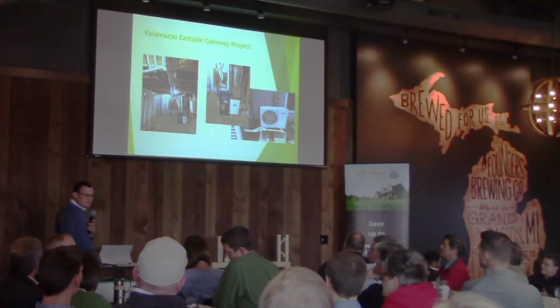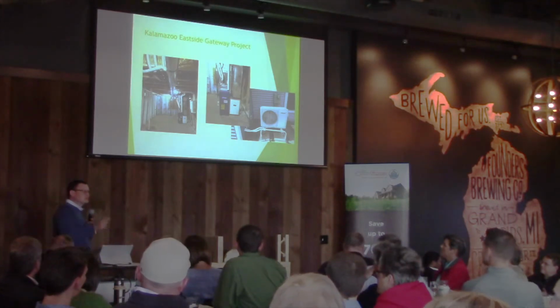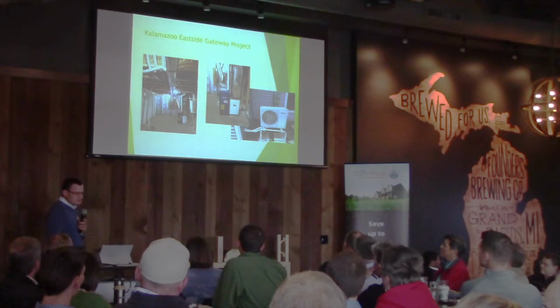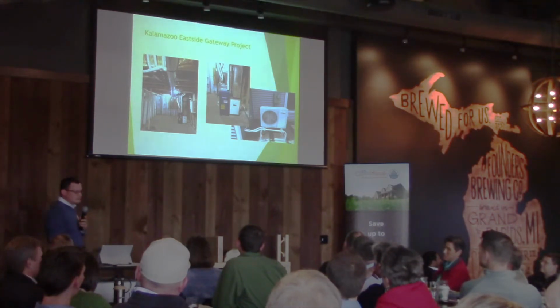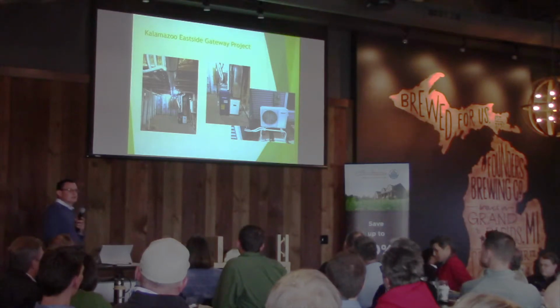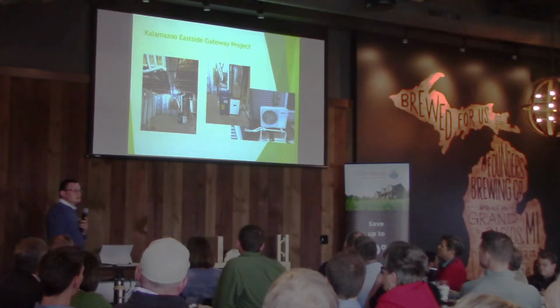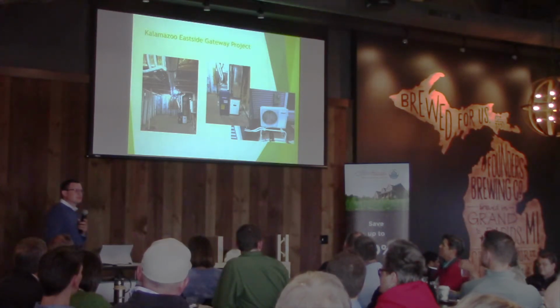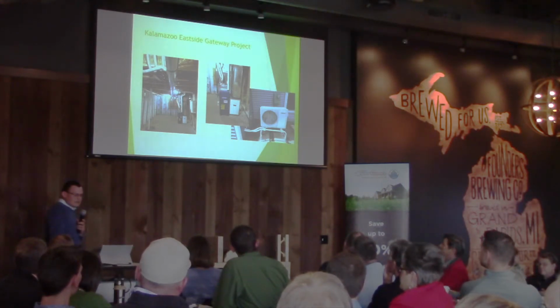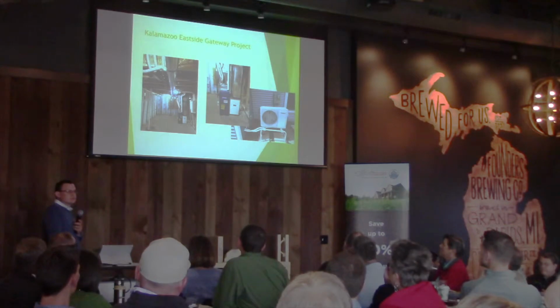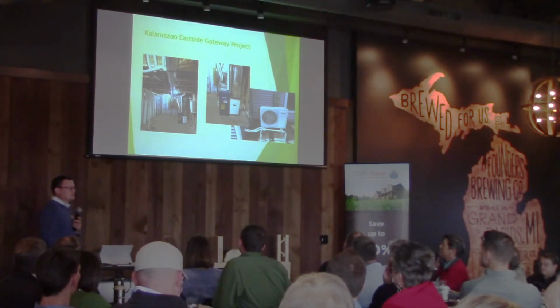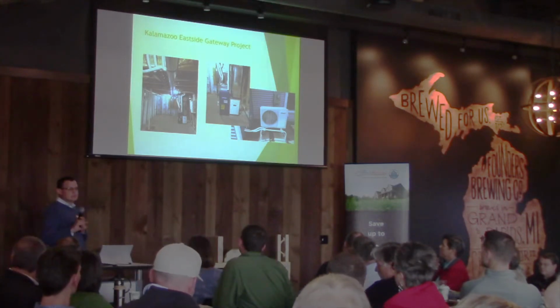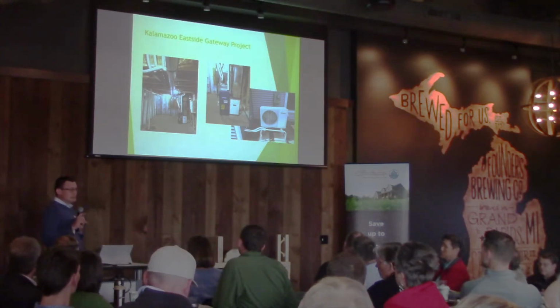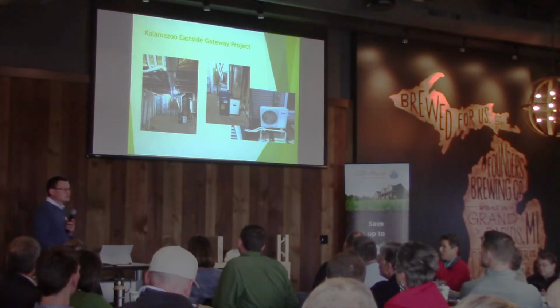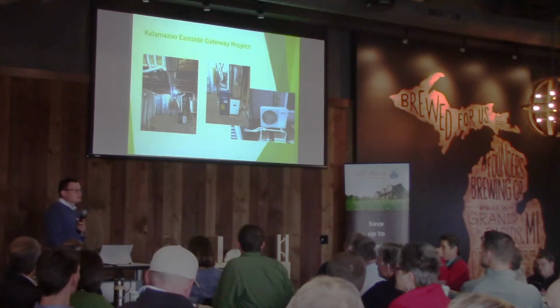On the supply side, the entire duct system runs through one 8-inch duct down the middle of the basement, and those little 2.5-inch duct runs you see are our supply runs to each room. It's a very small footprint—everything fits inside your walls. Usually we don't need any bulkheads in an entire house, and we can still get supply air to every single room. The other nice thing is it just needs a central return because our CFM is so low; we don't need return air in each room. You just need a 1/4-inch undercut under your door. Most doors, when pre-hung, come with a 1-inch undercut, so you're set there, and it can draw that air right underneath without any comfort issues.